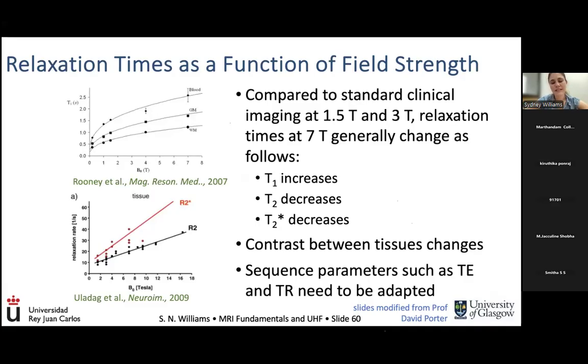It's not just an easy calculation, because the T1 relaxation, the amount of time it takes for those spins to recover to the main magnetic field, actually increases at ultra high fields compared to lower field strengths. And then the T2 times, the time of dephasing between those spins individually, actually decrease. So you have this opposite effect with T1 and T2 with field strength.